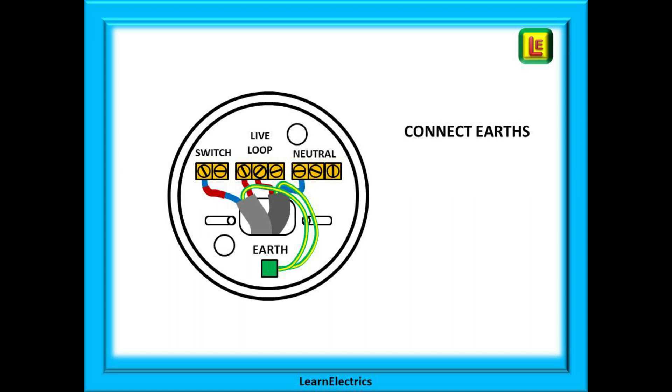We will have two earths as well, sleeve them separately and connect them together in the earth terminal. Do not leave them as bare copper. And finally, if not already in place, connect the two lamp wires.